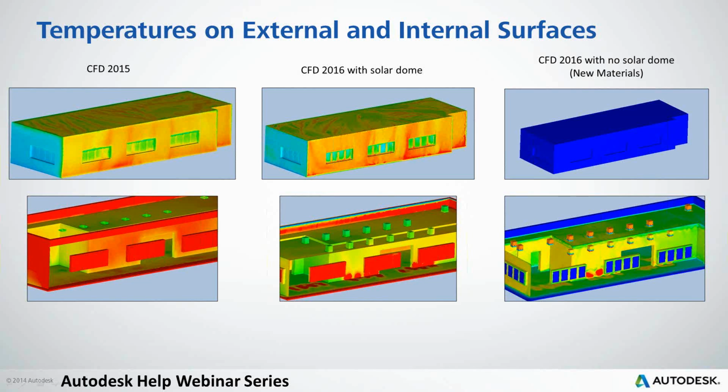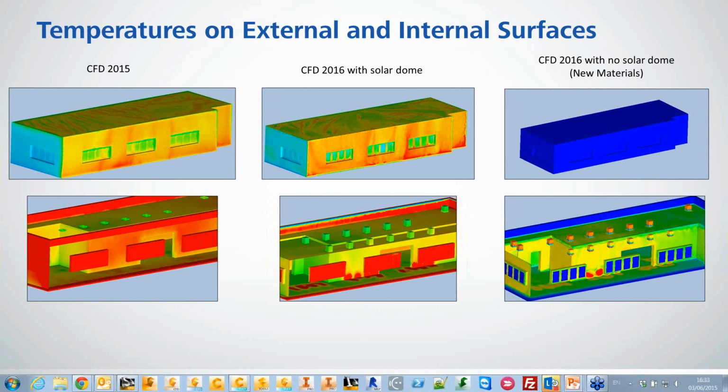Cool. Make that bigger. If you look at the bottom left-hand picture, you see that whole back wall is hot. In general, a lot of the internal room is going to be shown as a different temperature than actual in reality, because you would have pretty decent hot spots right where the windows are going to shine in, which we're showing in 2016 there. And it's going to reduce the overall room temperature and have a higher local spot.